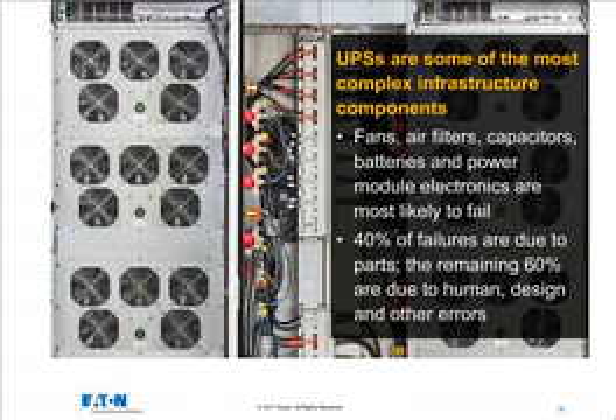So we need to be able to gather a great deal of data about those devices to make sure that we can come up with a reasonable scenario as to how it's going to perform over the next short or long period of time. 40% of UPS failures are due to parts. The remaining 60% are due to human error or, heaven forbid, design errors of that type of thing. Okay.